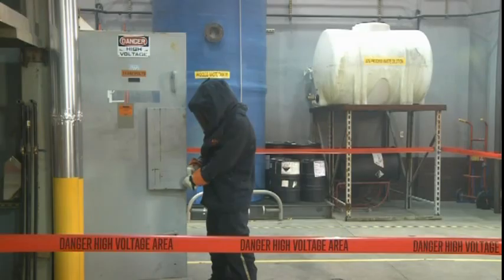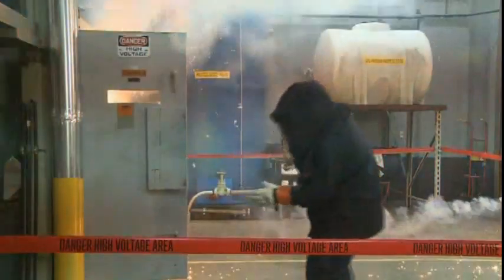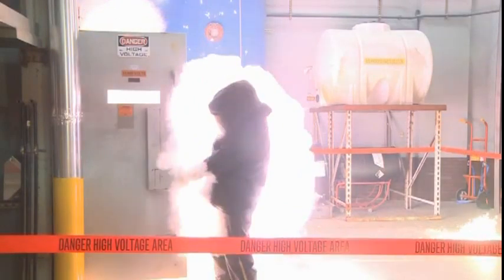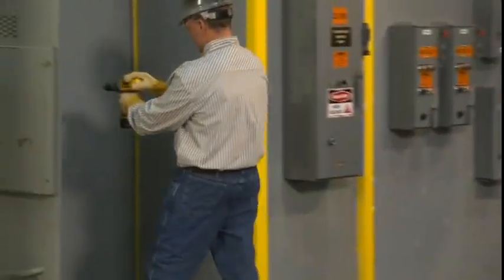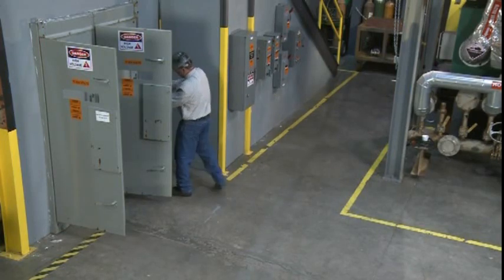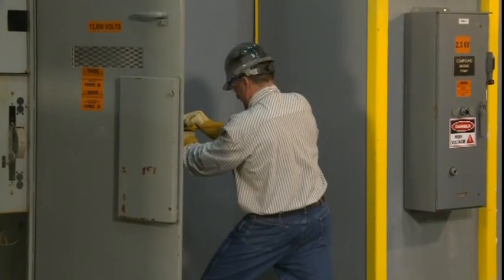There is one more very important boundary we need to explain: the arc flash boundary, which provides protection against the severe burns which may occur during an electric arc flash. An arc flash is a violent eruption of energy from an electrical source. An arc flash is often caused by the introduction of conductive material such as a tool or test lead leading to a flashover.